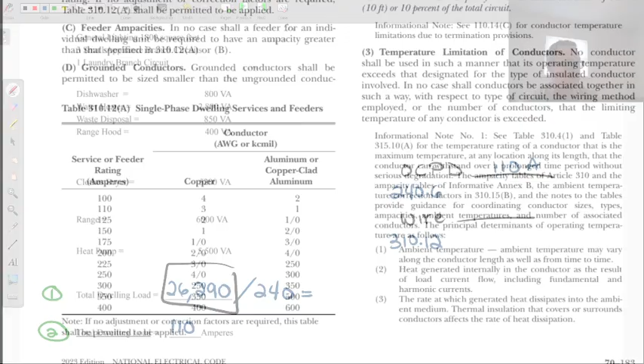It's really annoying, and I wouldn't have planned it this way, but the load that we calculated happens to also be a main breaker. But let's say this load was 105 amps. Again, we're not going to 310.16 with 105 amps, in the 75-degree column, looking for that wire. We find the main breaker first. Then we come here and the main breaker that we chose was 110. The wire that we're going to choose is a number 3.